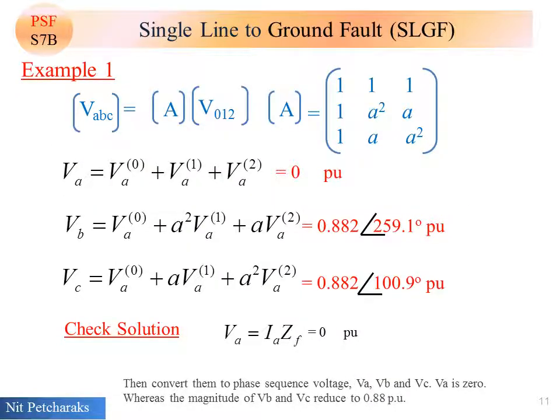Then convert them to phase sequence voltage VA, VB and VC. VA is zero. Whereas the magnitude of VB and VC reduced to 0.88 per unit.